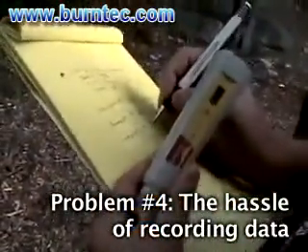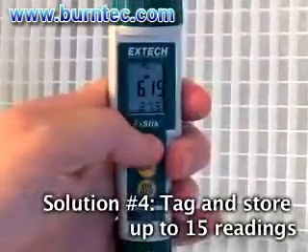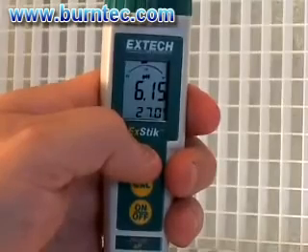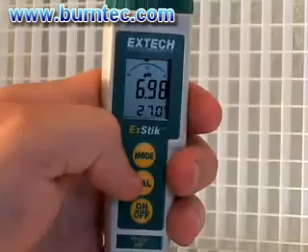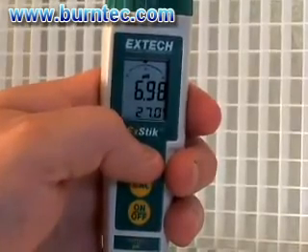Problem number four: Recording data on paper can sometimes be difficult when you are taking measurements out in the field, especially during times of unpredictable weather conditions. Solution: The built-in memory featured on the ExStik pH meter will record up to 15 measurements. Each stored reading will be labeled by a number for easy recall, eliminating the need to bring samples back to the lab. It not only saves time but provides maximum accuracy for on-the-spot data recording.